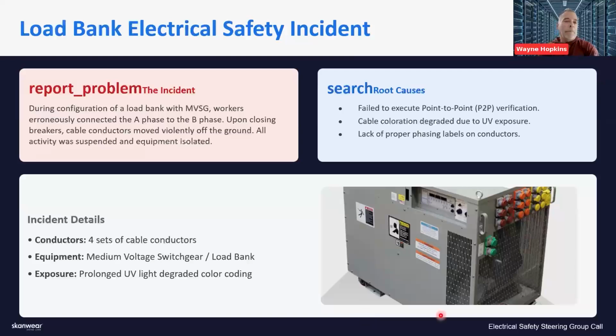For what happened on this one, the crews were getting ready to energize and load bank medium voltage switchgear. The workers, as they were hooking up their phases, had four sets of cable conductors, A, B, and C phase. While hooking those up, they inadvertently connected an A phase to a B phase and a B phase to an A phase.